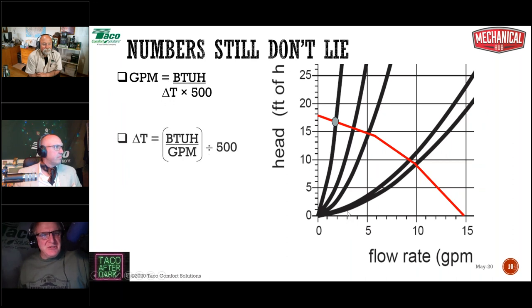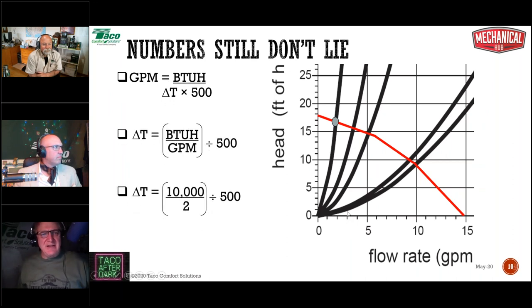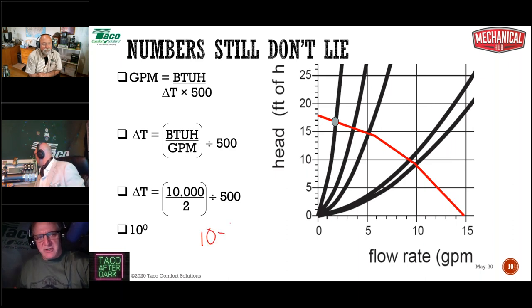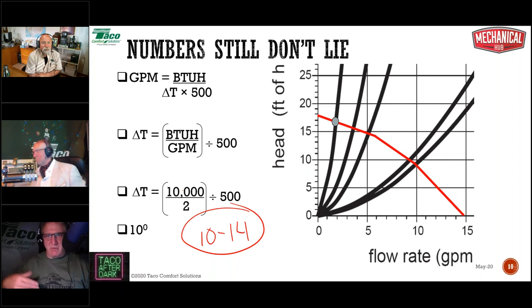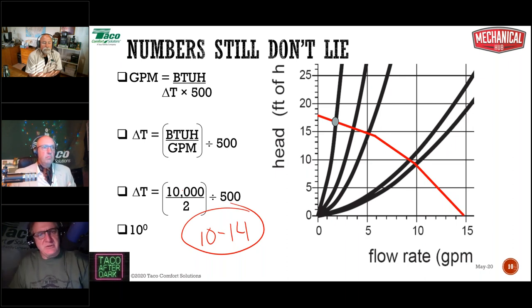So again, numbers still don't lie. We fill in the blanks, 10,000 divided by 2 divided by 500. Then we're talking about a 10 degree delta T. So again, the theoretical best delta T we're ever going to see in this system is going to be bopping back and forth between 10 and 14 degrees. So maybe the water's going out at 180, coming back at 170, or a low temperature boiler going out at 140, coming back at 130. Going out at 140, coming back at 126.